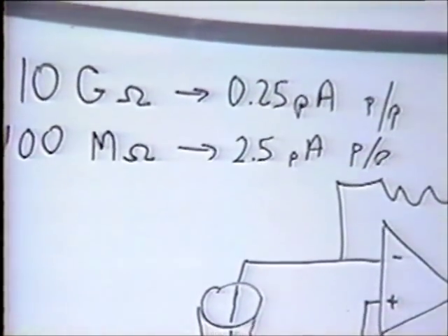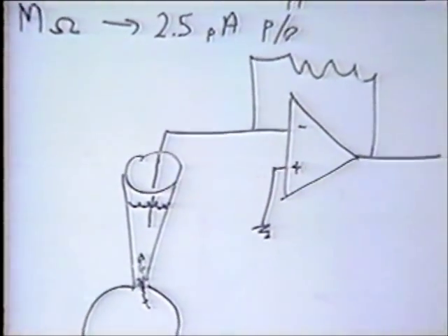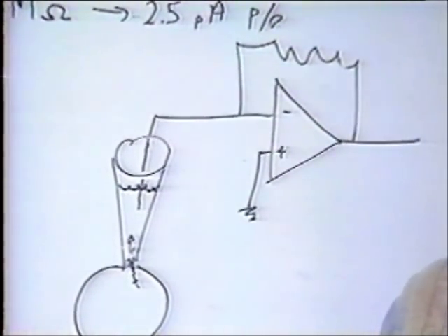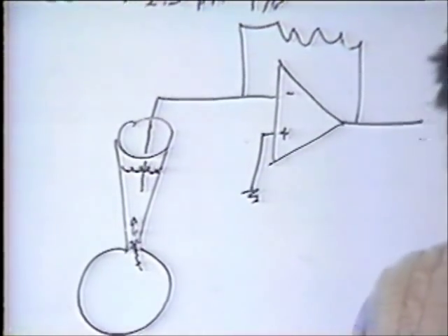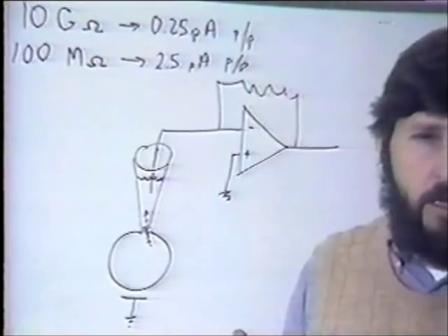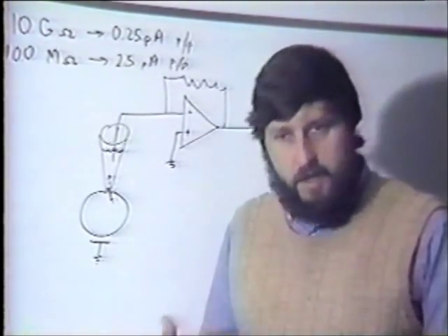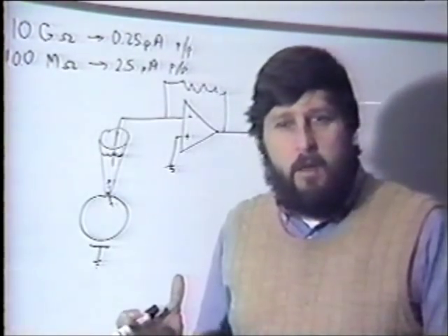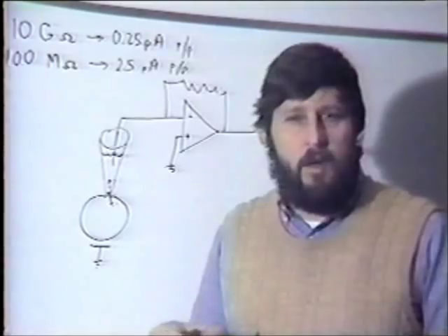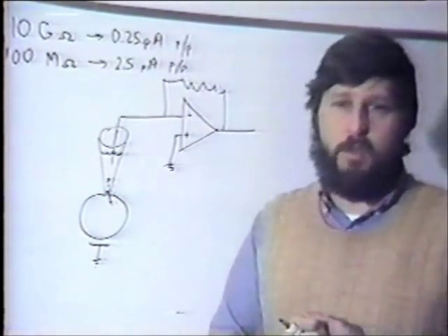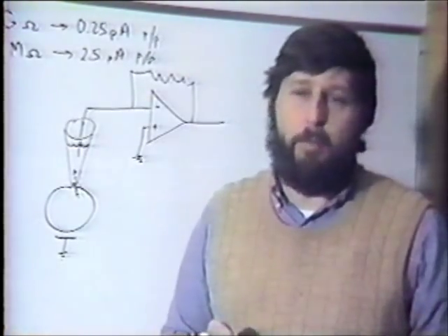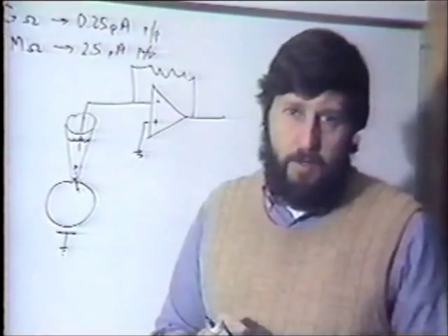Both elements have to be high resistance. It's easy to make the feedback resistor big just by choosing a feedback resistor. The seal to the cell is difficult to control, and we don't know what makes it good and what makes it bad. In general, if the cell surface is dirty or covered with connective tissue so that you can't bring the pipette close, you'll have a noisy seal. On the other hand, some cells seal under conditions where it would seem impossible — under the scanning microscope they have all sorts of protrusions, and it's very surprising that they seal. So you can't predict ahead of time, either from the electron microscope appearance of the cell or any other property we know of, whether it's going to seal or not.